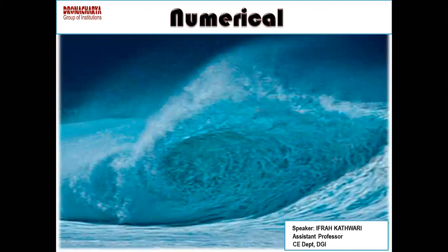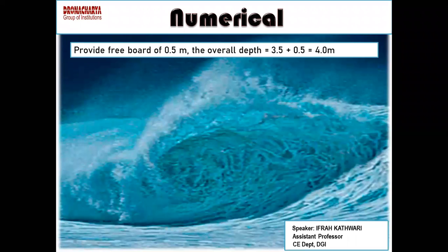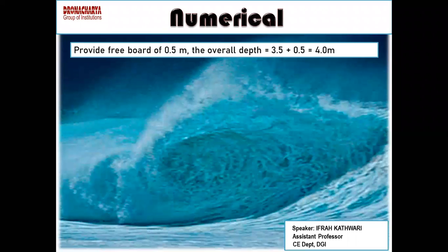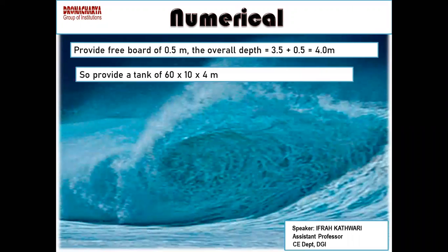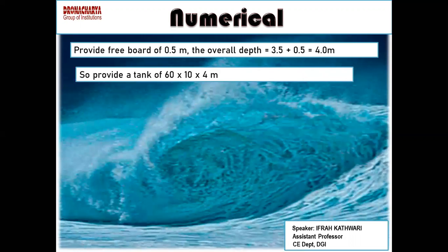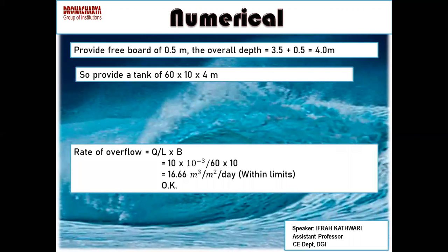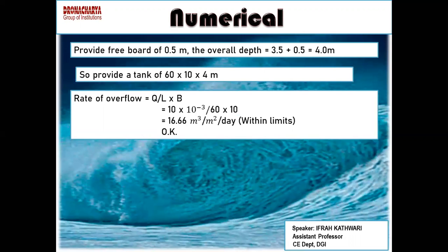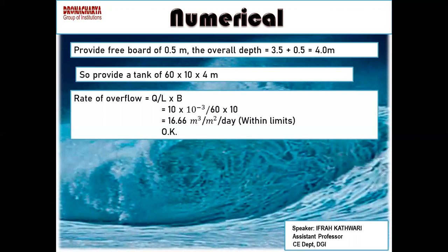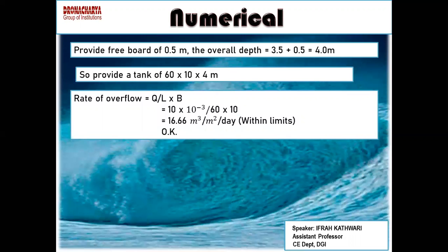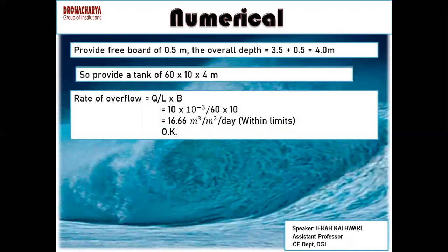So we are done with the volume of tank, taking the freeboard of 0.5. So this will be the tank to be provided. Okay, required tank. And rate of overflow is again 16.66 in this question as well. So it's within the limit.